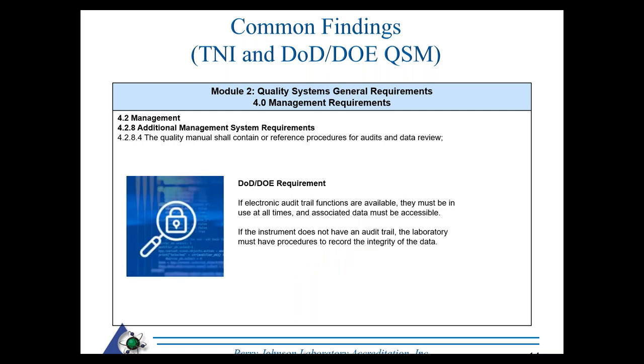The DOD/DOE quality manual must also document that an electronic audit trail function is available when reviewing or auditing data. Assessors will ask analysts to show that the electronic audit trail function is enabled on their instruments. For instruments without that capability, there must be some evidence of data integrity — either through the internal audit or data review process — with a procedure on how that's handled.